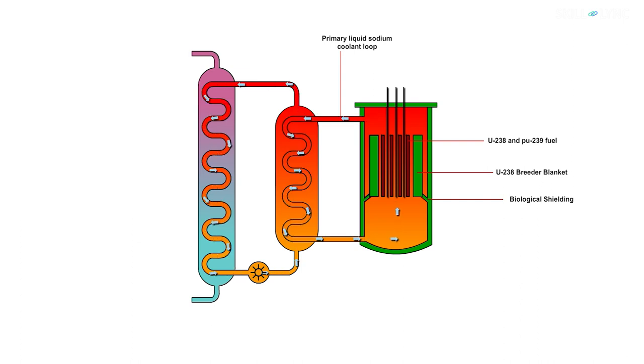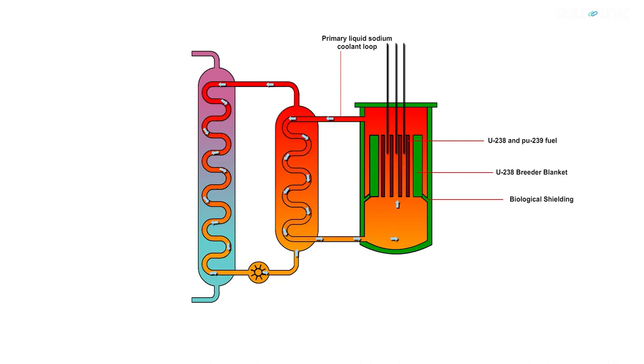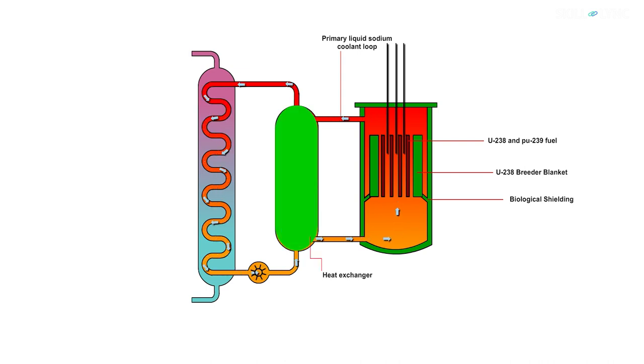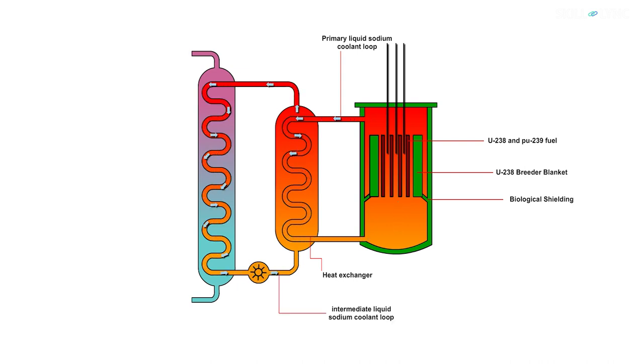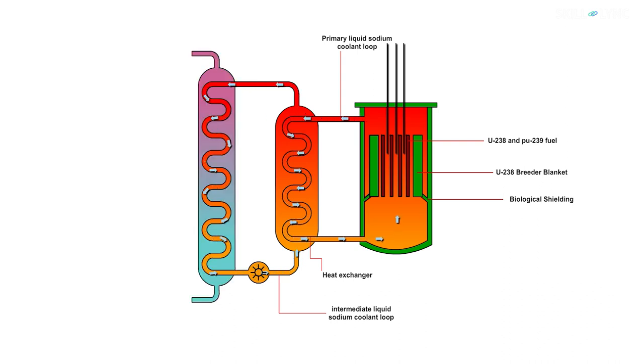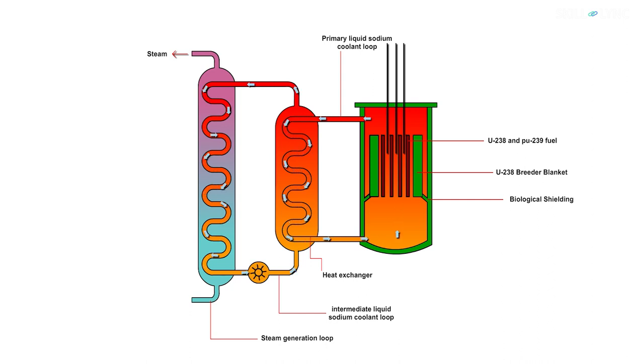As the nuclear fission occurs in the core, the liquid sodium in the primary loop transfers the heat to the intermediate liquid sodium loop through a heat exchanger. The intermediate loop has liquid sodium as coolant. The heat from the liquid sodium in the intermediate loop is used to generate steam from water in a steam generator. This steam is further sent to drive a turbine and returns as water through a condenser.